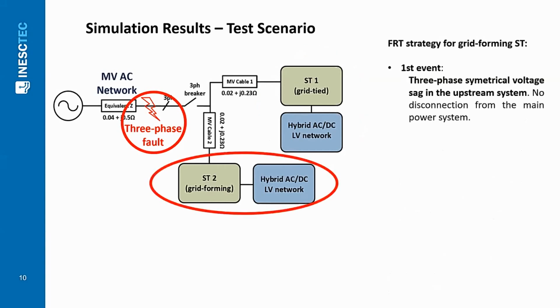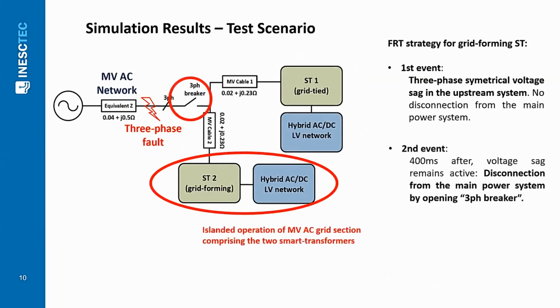Regarding the evaluation of the fault ride-through strategy for the grid-forming smart transformer, two stages are considered. First, a three-phase fault is simulated in the upstream system, without disconnection of the small medium voltage grid from the main power system. After 400 milliseconds, with the fault still active, the medium voltage grid is disconnected from the main power system by opening the three-phase breaker in order to isolate the small medium voltage grid from the fault. In this case, the grid-forming smart transformer is expected to support the islanded operation of the small medium voltage grid without power interruption.